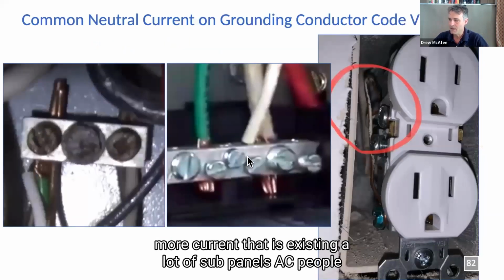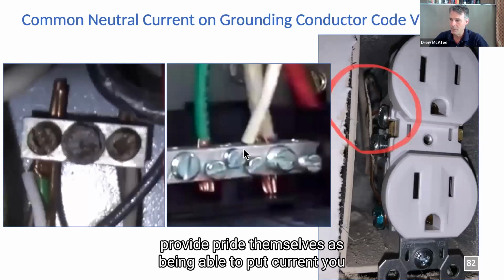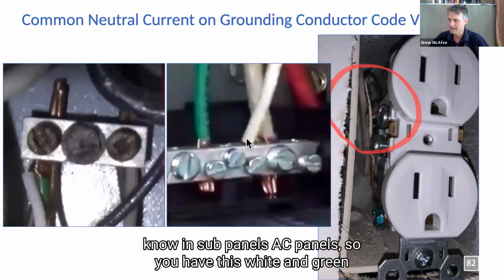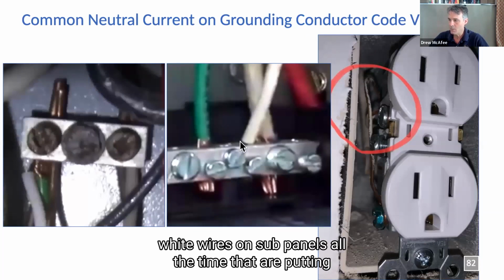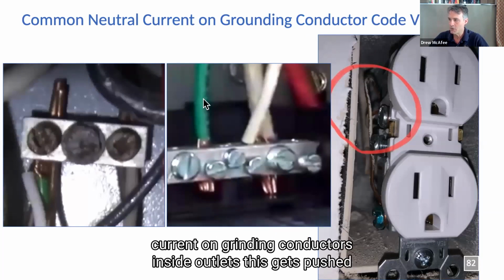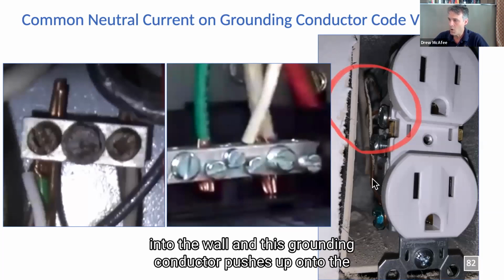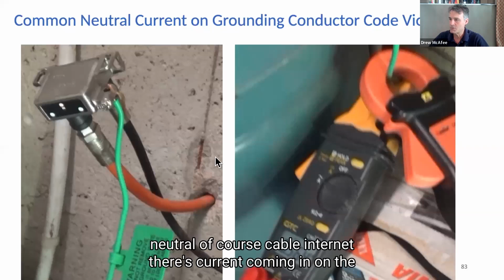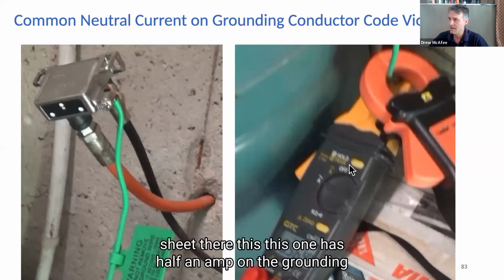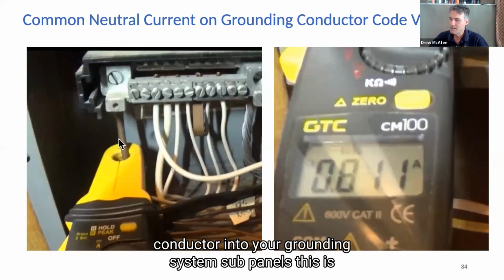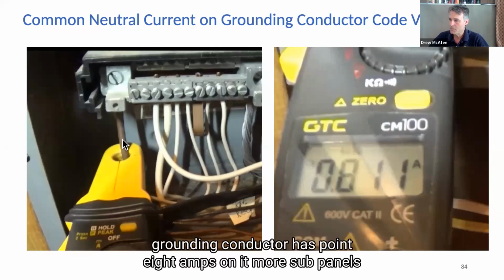A lot of AC people pride themselves on being able to put current in sub panels. So you have these white and green wires on sub panels all the time that are putting current on grounding conductors. Inside outlets, this gets pushed into the wall and this grounding conductor pushes up onto the neutral. Of course, with cable internet, there's current coming in on the sheath. This one has half an amp on the grounding conductor into your grounding system. On this sub panel, the grounding conductor has 0.8 amps on it.